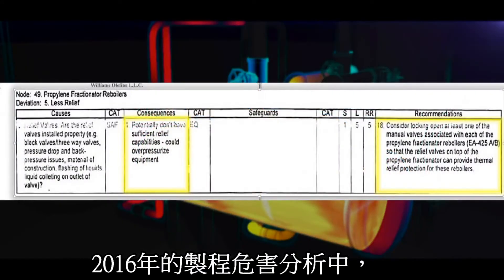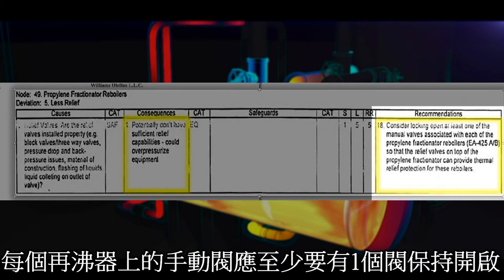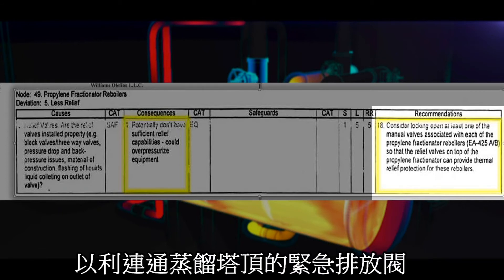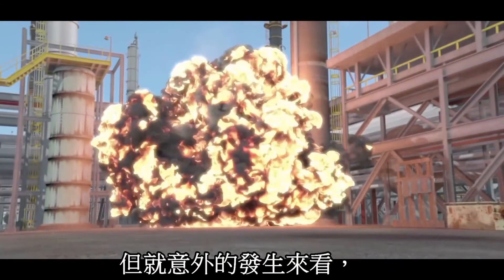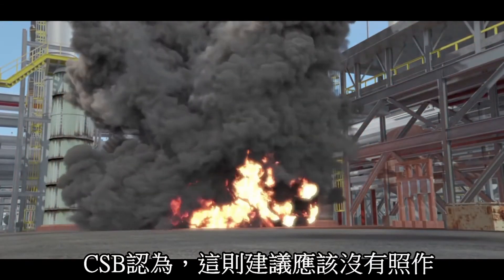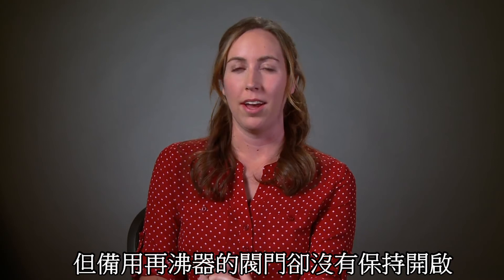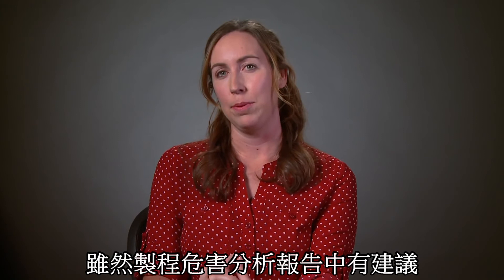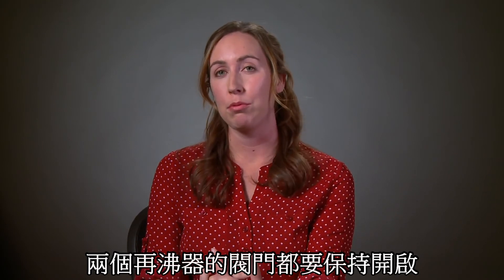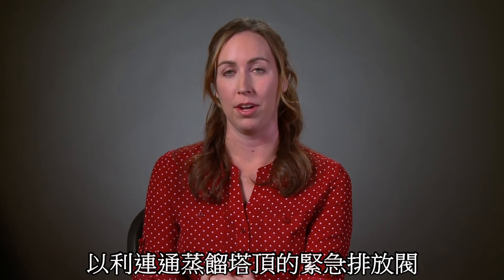An internal recommendation from the 2016 PHA stated: 'Consider locking open at least one of the manual valves associated with each of the propylene fractionator reboilers.' While that recommendation was marked as complete, the CSB found it was not implemented as intended. A process valve on the operating reboiler was locked open, but a process valve on the standby reboiler was not, even though the PHA recommended that valves on both reboilers should be locked open so that the reboilers had an open path to pressure relief.